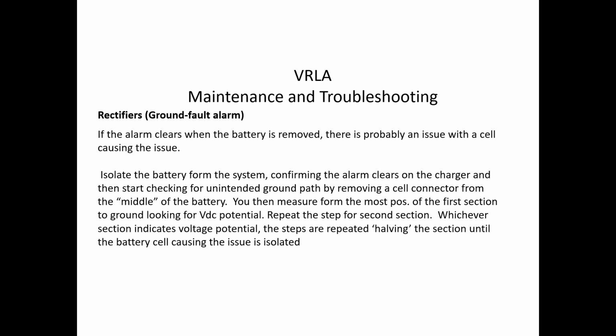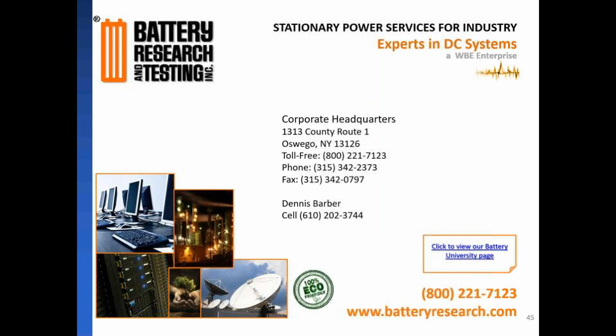And then we had also talked about if the alarm is detected at the battery, we recommend using a voltmeter and checking the battery's most positive and most negative to a ground source. Typically the racks are grounded, or that steel tray that the battery is installed in is grounded. We remove the intercell connection from, say, jar 30 to 31 or 29 to 30, somewhere in between, and we kind of break the battery in half and try to isolate. We're looking for voltage potential from that half of the battery to the tray, and then just keep shortening it down, trying to track it down. Ground faults are not fun.